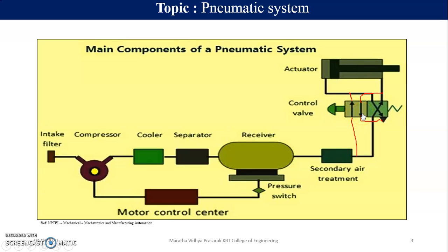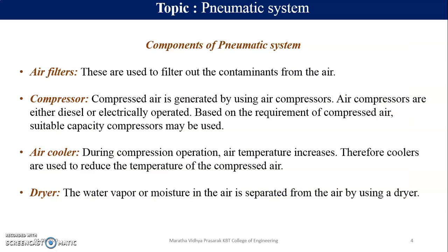Okay, so these were the basic components which make a complete pneumatic system. And this is very simple to understand. This is a piston head, this is a piston rod head, and this is a double acting cylinder. Why do we call it a double acting cylinder? Because here there is port A and here there is port B. So जब यहाँ extend करना है तो एक signal लगेगा, retract करना है तो फिर से अलग signal लगेगा. It is not spring operated, so it is not going to retract on its own, which happens mostly in single acting cylinders.